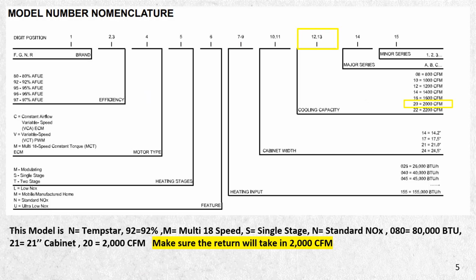Now, on the nomenclature of these furnaces, the one that I have with me that I take around and show and do these classes on is a 92% furnace. So the numbers at the bottom will kind of go into that. But here's this first number is your N, which is your brand, which is Tempstar. We have an N model and we have an R model, but this is the N that I have with me. And then this point, these two figures here will be 92. So it's an N Tempstar 92% furnace. We move over, what kind of motor does it have? This one is the M, which is the multi 18-speed constant torque. That's in this position. And here are heating stages. We have a single stage gas valve that's here.